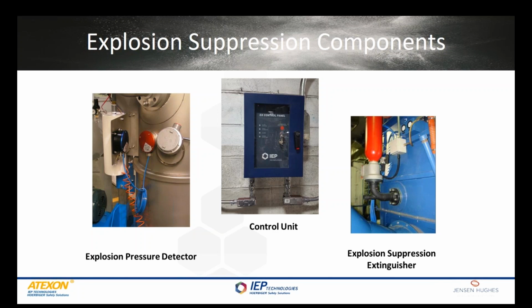Control panels pick up the signal from the detectors. They signal the extinguishers to discharge. They also signal the process to shut down so that you stop any equipment that moves product or air through the protected volume. And then finally, the extinguishers are typically high pressure extinguishers that are filled with a sodium bicarbonate based dry chem. Extinguisher discharge velocity can be approaching 200 feet per second. So you get a very, very fast rate of agent discharge within the protected vessel to extinguish the deflagration in its very early stages.